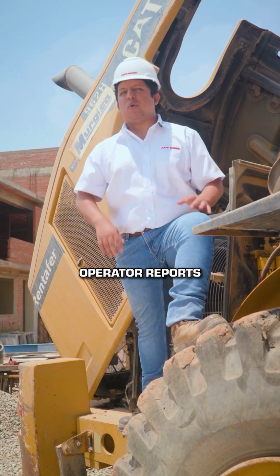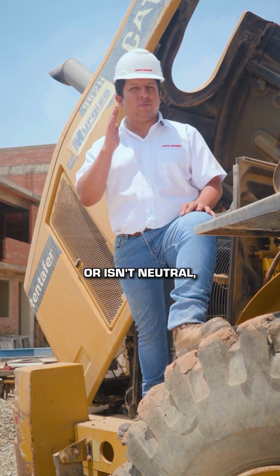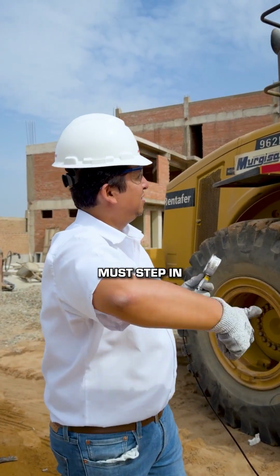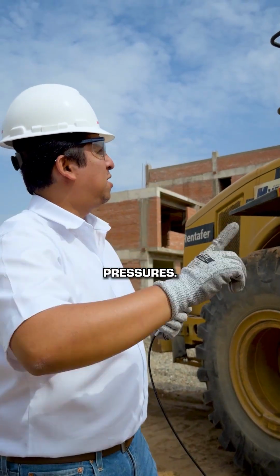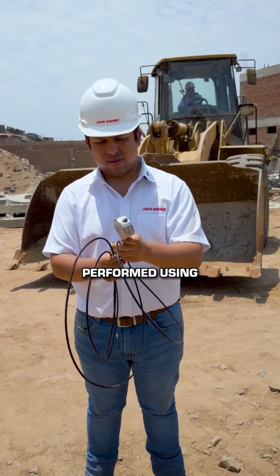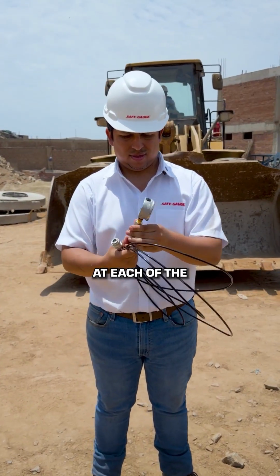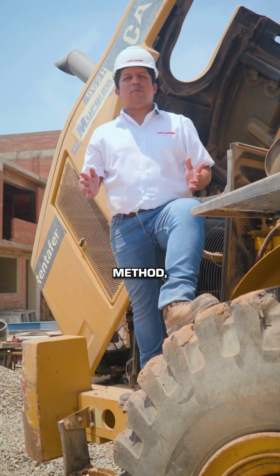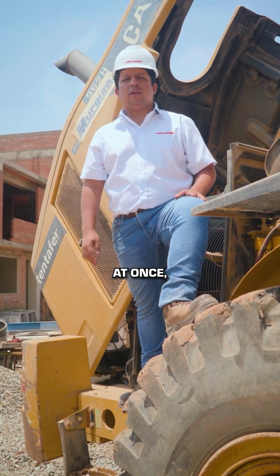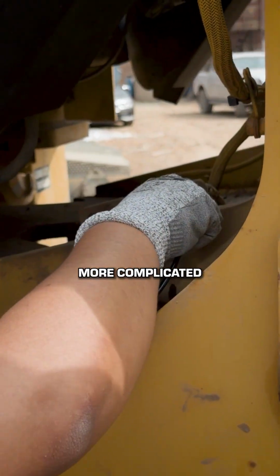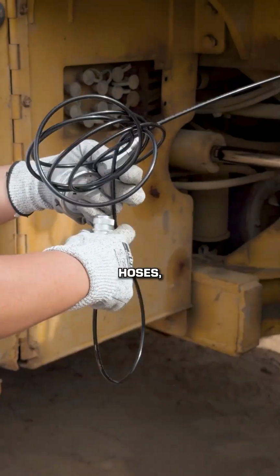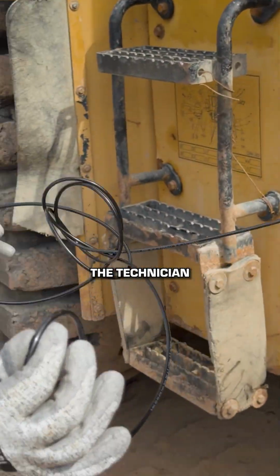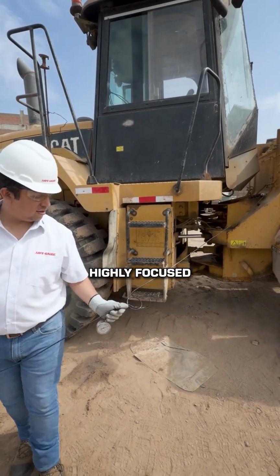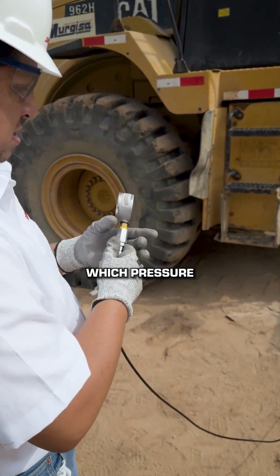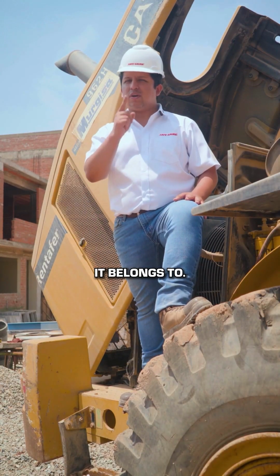When the operator reports that the loader isn't moving or isn't neutral, a technician must step in to evaluate the system's pressures. This evaluation is performed using pressure gauges and test lines at each of the test points. With the traditional method, you can measure several pressures at once, but the diagnosis starts to get more complicated than it should. Between gauges, hoses, and connections, the technician has to be very organized and stay highly focused to avoid confusing which pressure they're seeing and which circuit it belongs to.